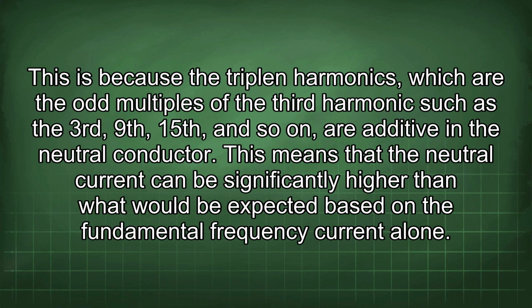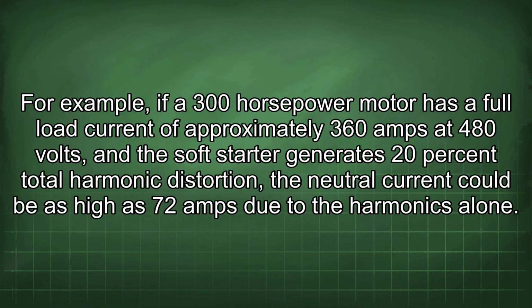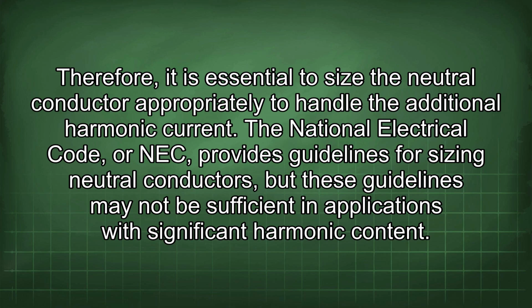This is because the triplen harmonics, which are the odd multiples of the third harmonic such as the 3rd, 9th, 15th, and so on, are additive in the neutral conductor. This means that the neutral current can be significantly higher than what would be expected based on the fundamental frequency current alone. For example, if a 300 horsepower motor has a full load current of approximately 360 amps at 480 volts, and the soft starter generates 20% total harmonic distortion, the neutral current could be as high as 72 amps due to the harmonics alone. Therefore, it is essential to size the neutral conductor appropriately to handle the additional harmonic current.